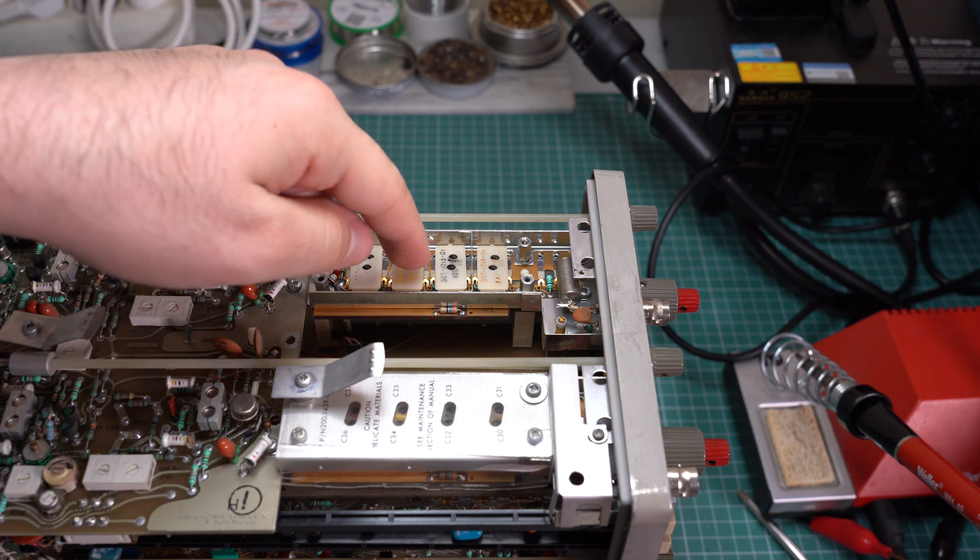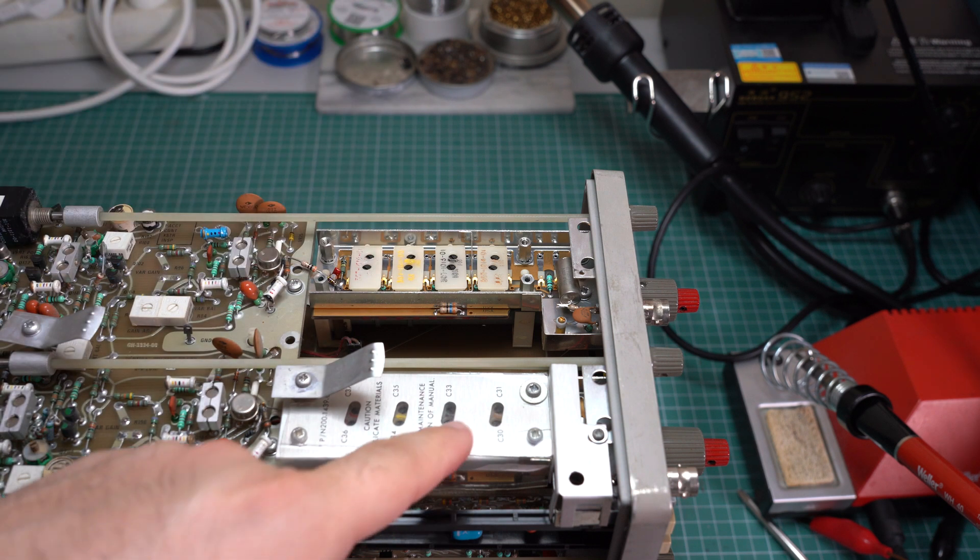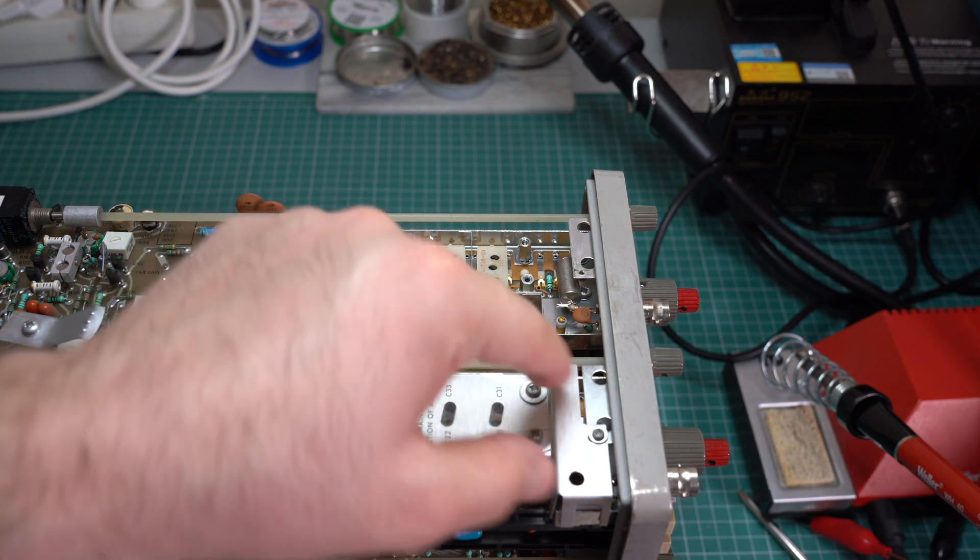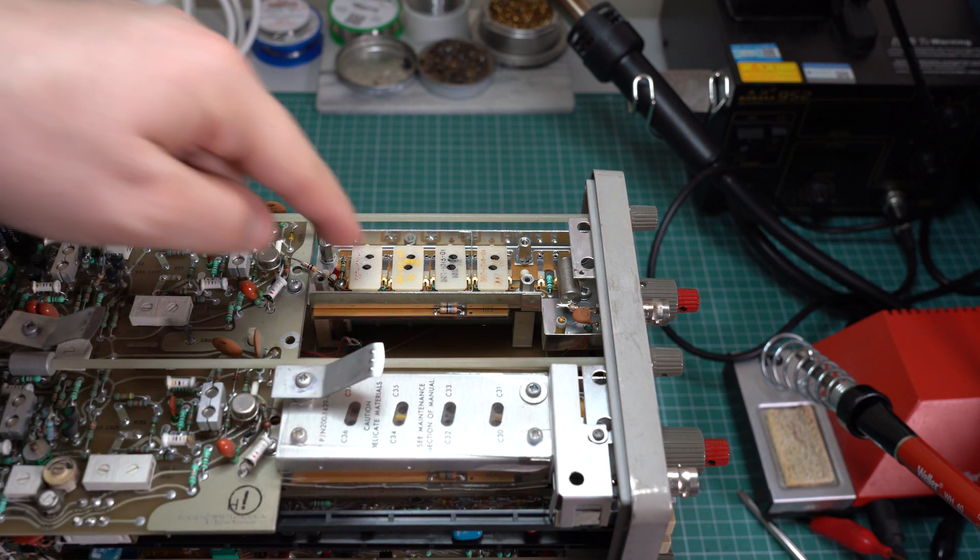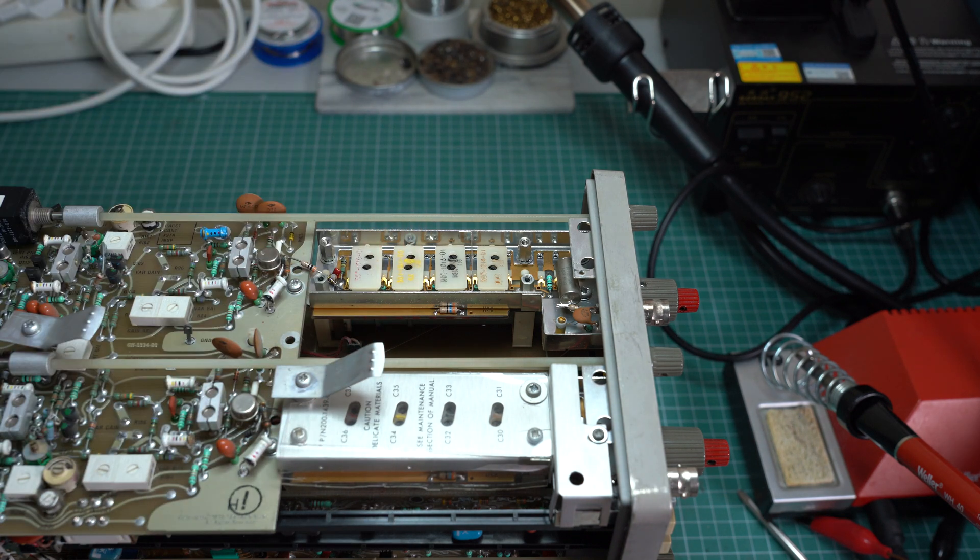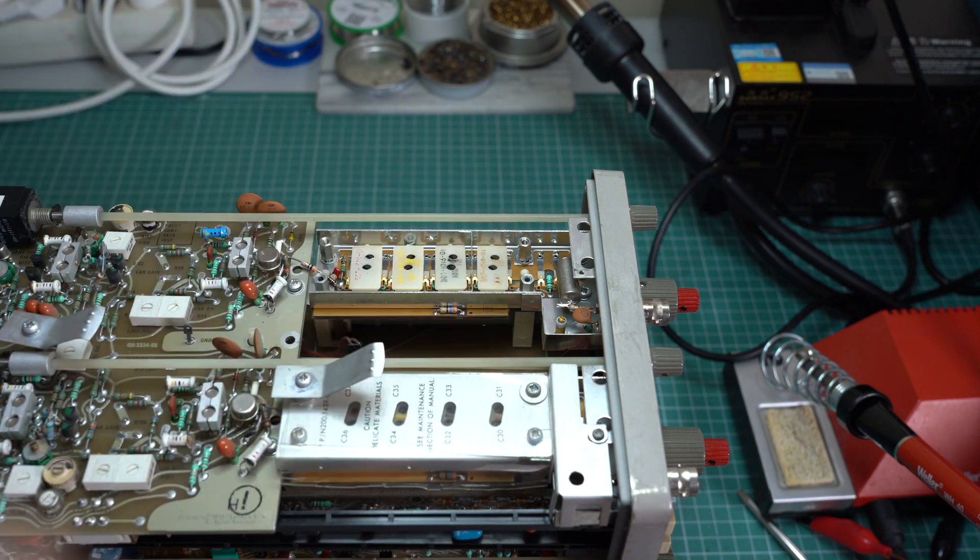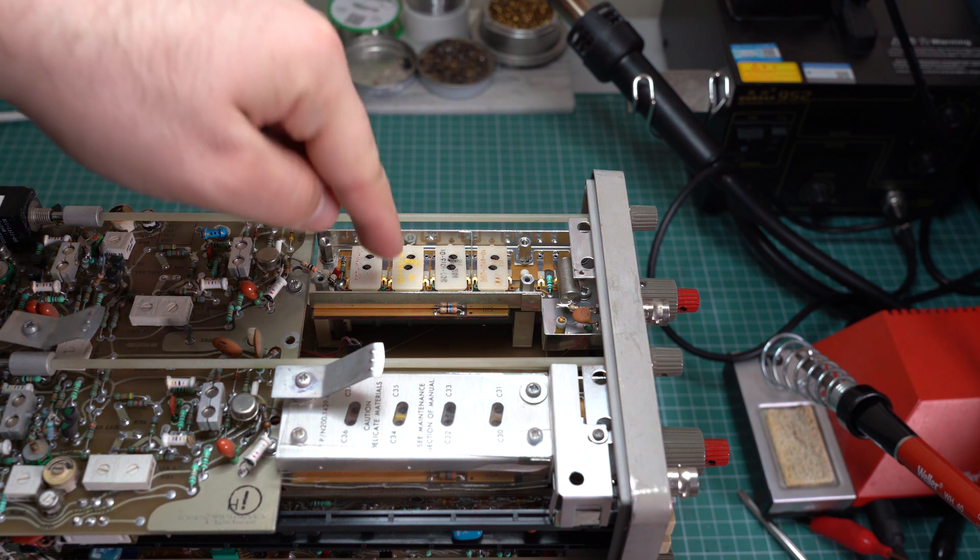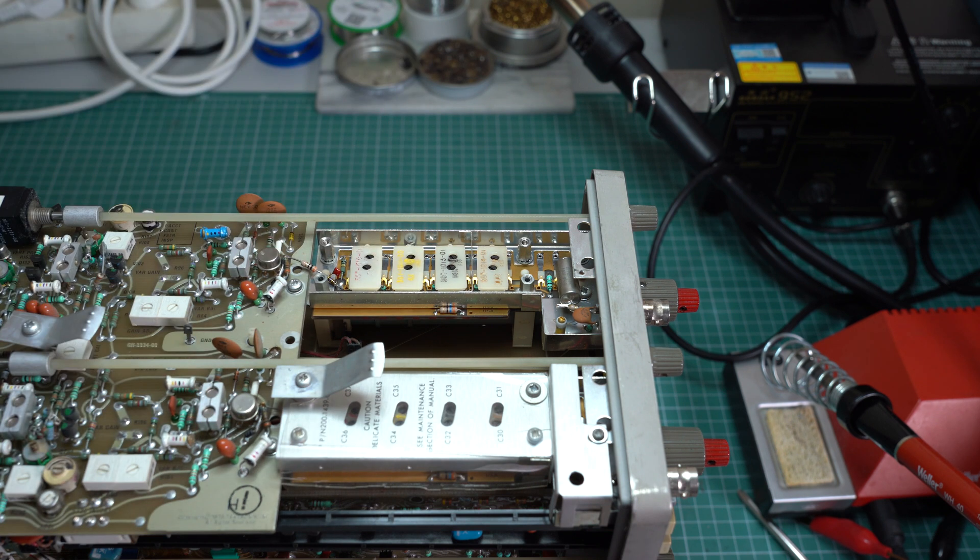Now these modules are socketed. So in order to confirm that this one is blown, my plan is to open up the second attenuator, this is for the second channel, and swap the modules. Or maybe just put this one into the other channel to see if the fault moves to the second channel. And if it does this isolates the fault to this module here. So let's give this a try.